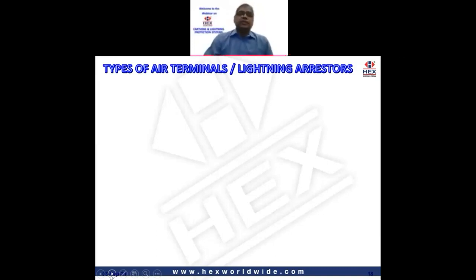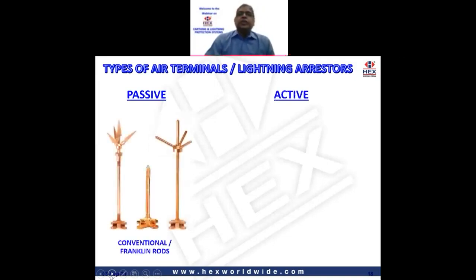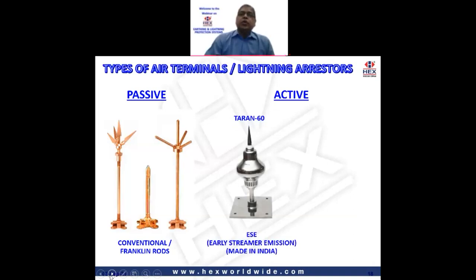We have the passive and the active lightning arresters. What are passive? Passive are the conventional Franklin rods. They come in single point or multiple point models. We have them in copper or copper bonded steel, brass and solid copper. Now in the active range, we have the early streamer emission, or ESE, arresters. Now this is the Taran-60 model, which is a second generation ESE. It is purely mechanical and has been designed and developed here in India, like I said earlier.